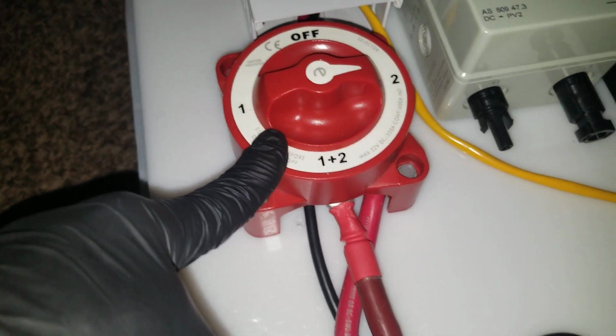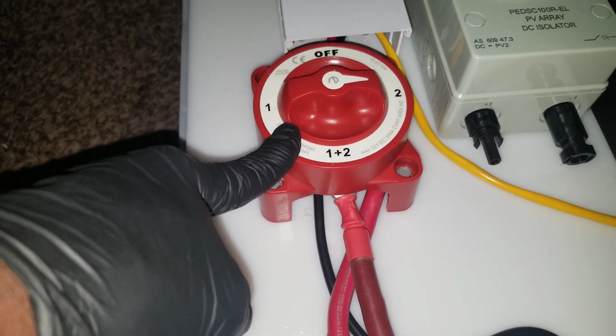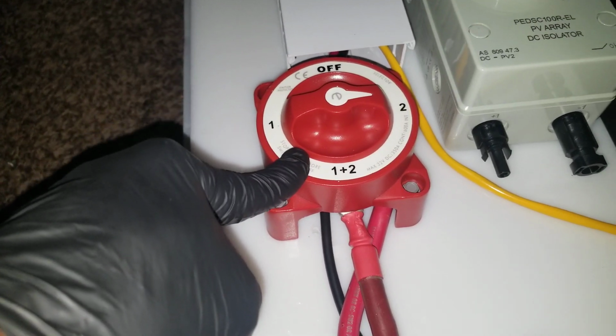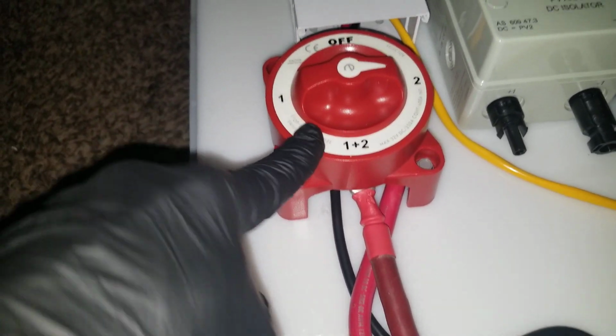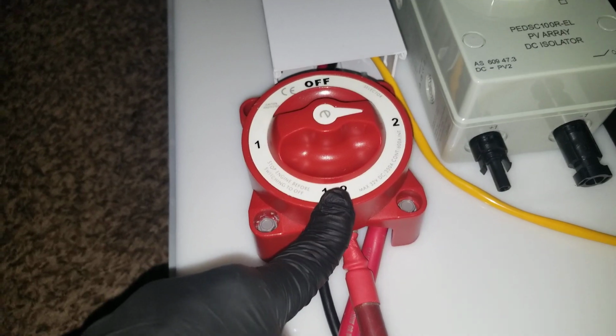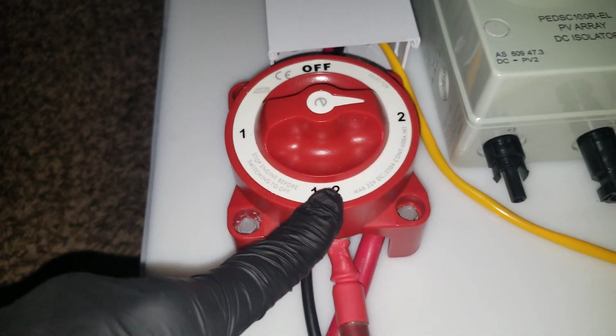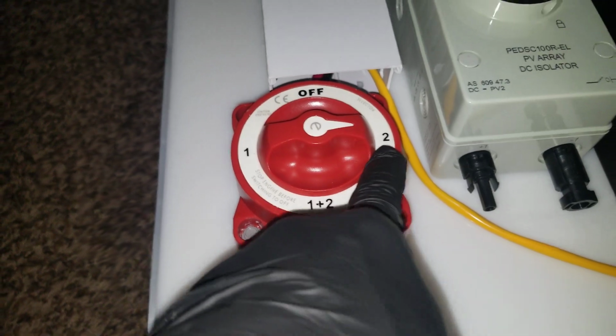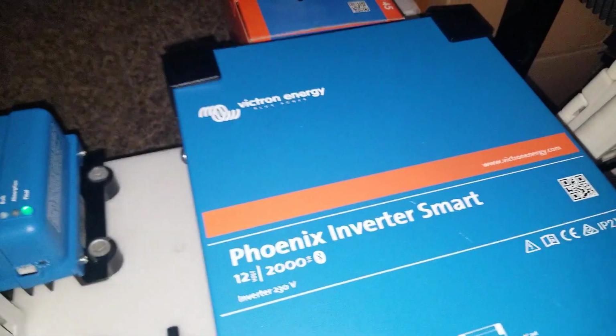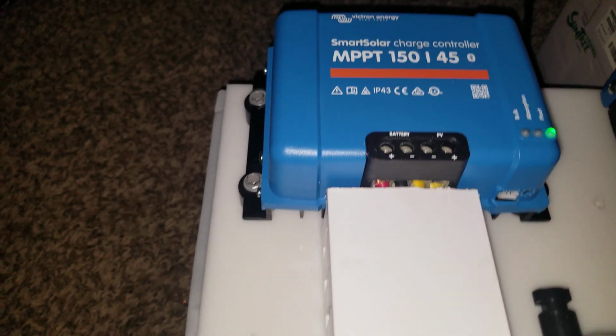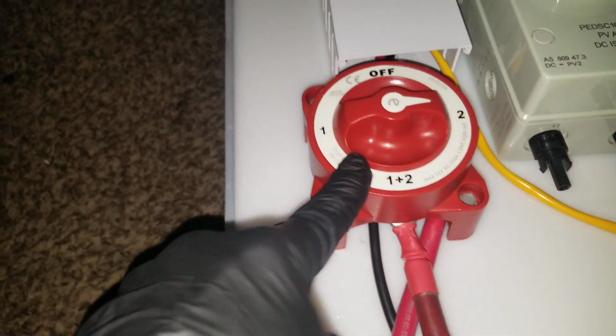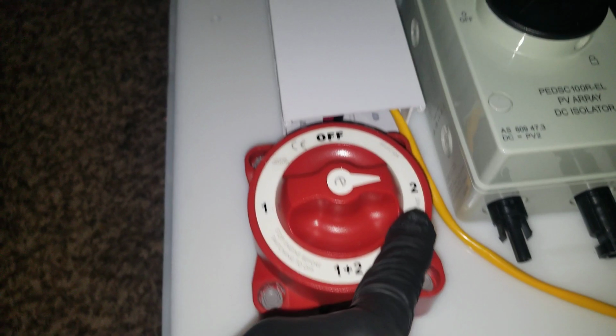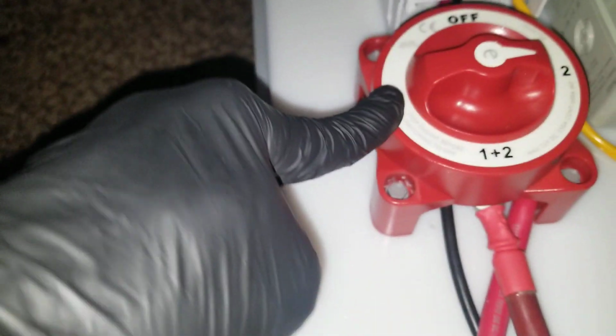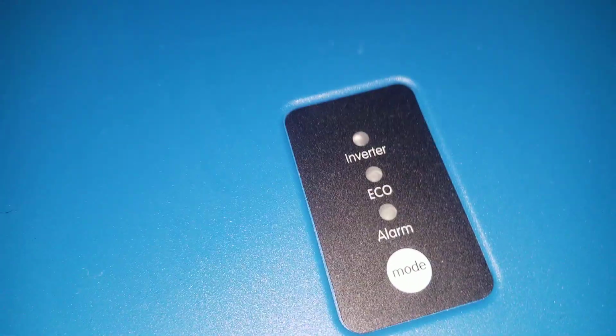Then I have a disconnect termination point right here into a Blue Sea marine battery isolator or disconnect. It has 2 disconnects - I can isolate the inverter right here, and I can isolate the charge controller. Right now number 2 is for the charge controller, and number 1 is for the inverter. So if I put in 1 and 2, I have both devices on.